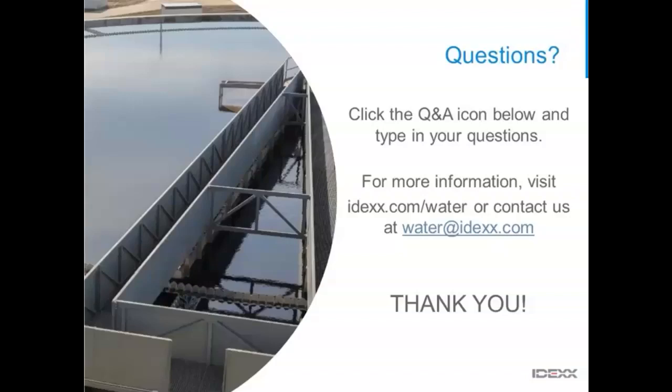Okay, and the next question is for you, Sean. If I have a sample that has turbidity or sediment, can I use that sample? Yep. Samples with turbidity and sediments could be done. We suggest that if there's any question about the turbidity interfering with the read, then it's probably best to do some kind of dilution, and that would take care of that turbidity and be able to make it a little clearer to read if there's any kind of concern that they would have any kind of color.